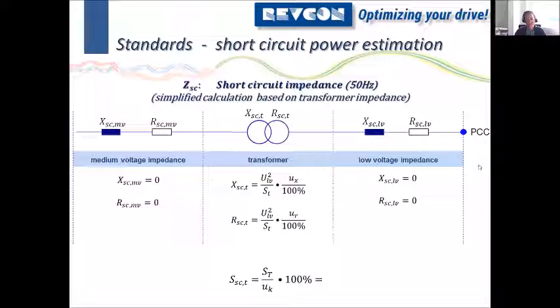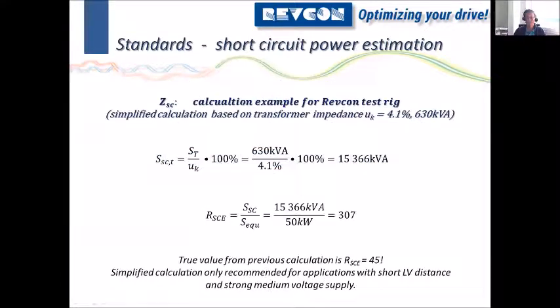However, if you ever get in the situation where you have these values, but you don't know exactly how to calculate the short circuit impedance, send the values to us. We will calculate and we will tell you what is your short circuit power ratio, whether you need harmonic mitigation. Or if you don't need it, we will tell you don't need to add anything. So I think we are quite fair in that area. That's something that we will always offer. Or you will get this presentation, so you could give it a try first, and you could get us to confirm the values that you have calculated. Maybe that's another option.